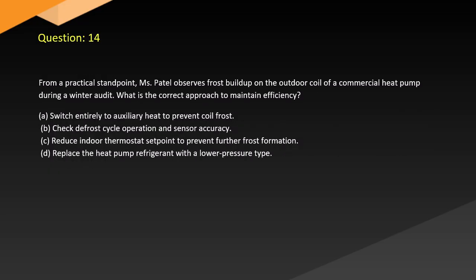Question 14. From a practical standpoint, Ms. Patel observes frost build-up on the outdoor coil of a commercial heat pump during a winter audit. What is the correct approach to maintain efficiency? A. Switch entirely to auxiliary heat to prevent coil frost. B. Check defrost cycle operation and sensor accuracy. C. Reduce indoor thermostat set point to prevent further frost formation. D. Replace the heat pump refrigerant with a low pressure type.